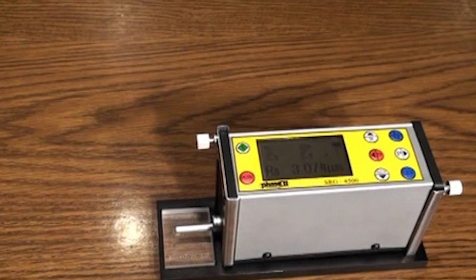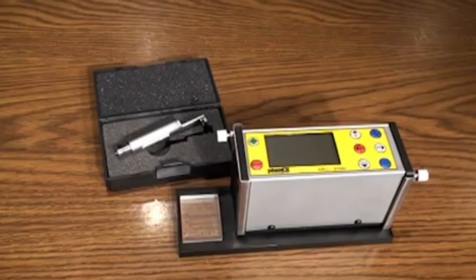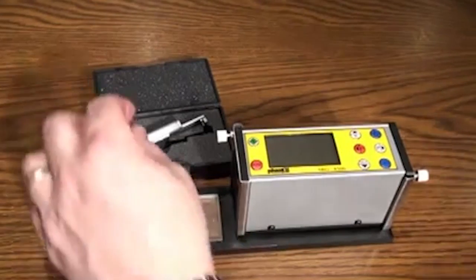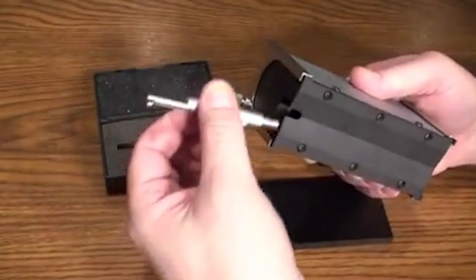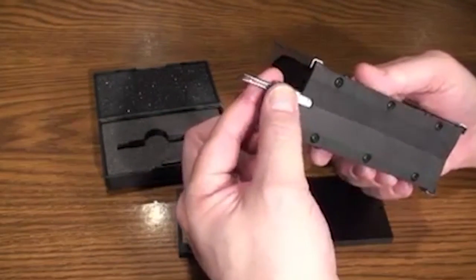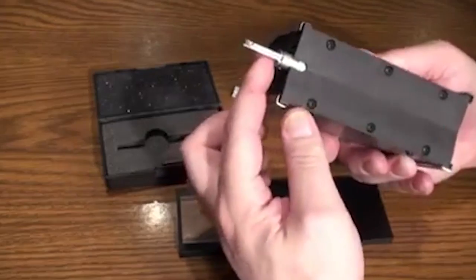As you can see, the SRG-4500 is a handheld battery-powered instrument with graphic display and controls on top and an extended stylus which will retract and extract upon taking surface roughness samples automatically. To begin, insert the stylus that is supplied in a separate container for optimum protection. Make certain to line up the plug and press easily into the socket.